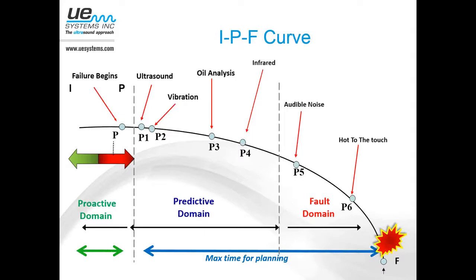I'm sure many of you have seen this curve in varying configurations. I personally really like this version of it because it adds in the I. For those of you who are not familiar with this, the P to F curve is really just a visual representation that lets you look at the point that a failure can be detected in an asset to the point where you have full functional failure, and some typical technologies and where they fall on the timeline of when that failure can be detected. So you take two of the technologies up at the top here, the ultrasound and the vibration, which are very early on in the process of a failure, from when you can find it to when it fully functionally fails, all the way down to where once something is smoking or it's hot to the touch or you hear it audibly, that's way down on the curve.